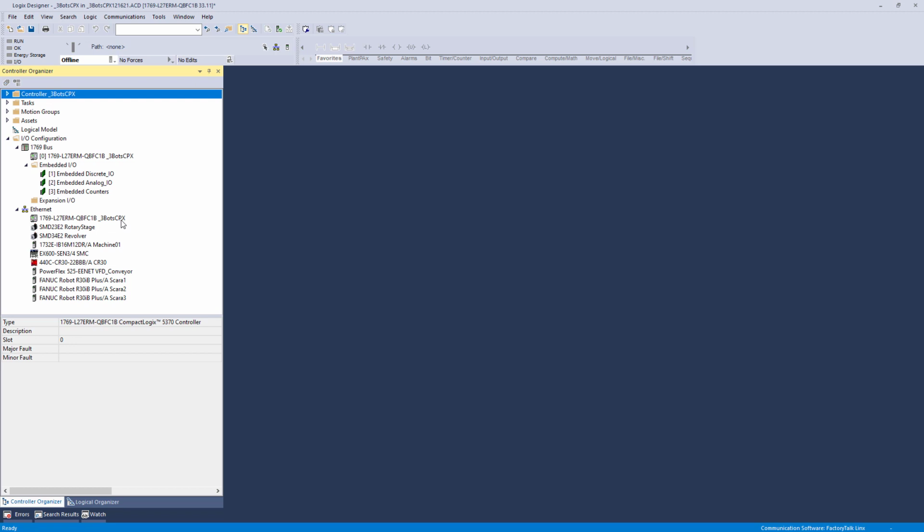First, we have our processor. And up here is the processor right here. The processor is plugged into the bus. Okay, and then you go across the bus to the embedded I/O or expanded. Also, this processor has built into it redundant Ethernet, which means it has two RJ45 connectors on the front edge underneath where you can't see them.